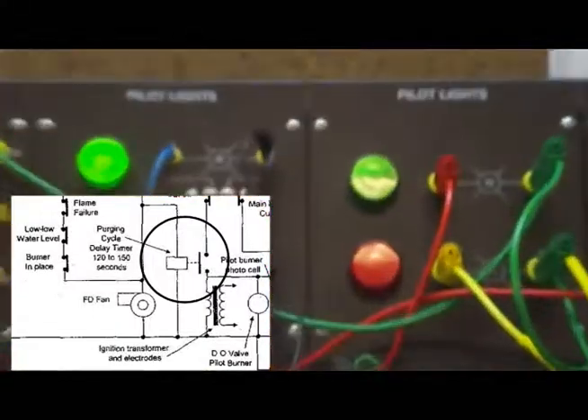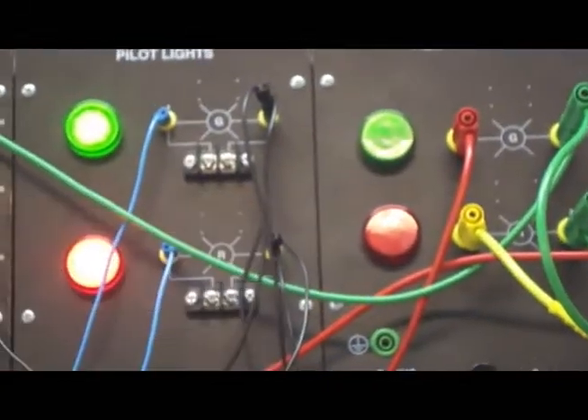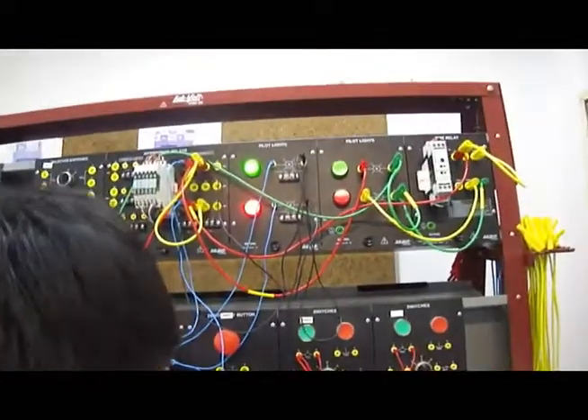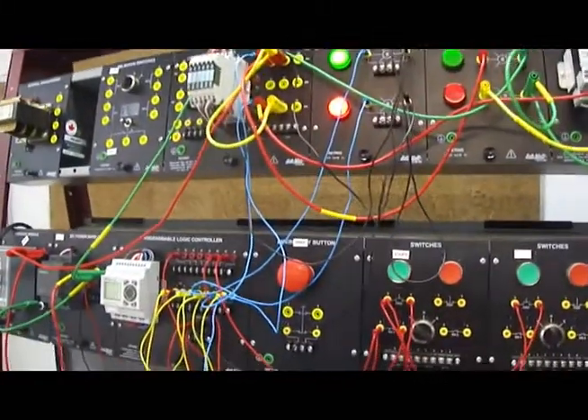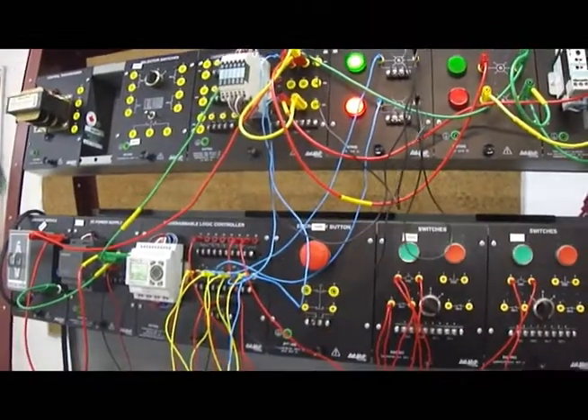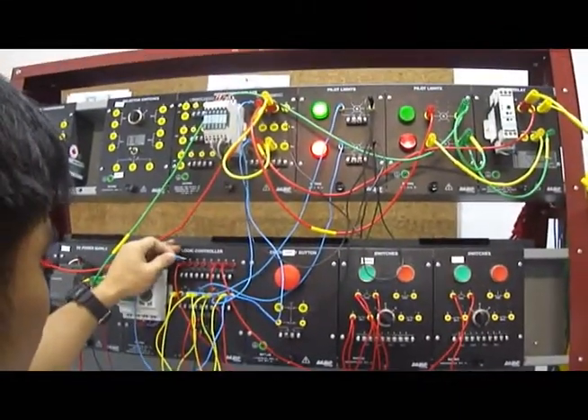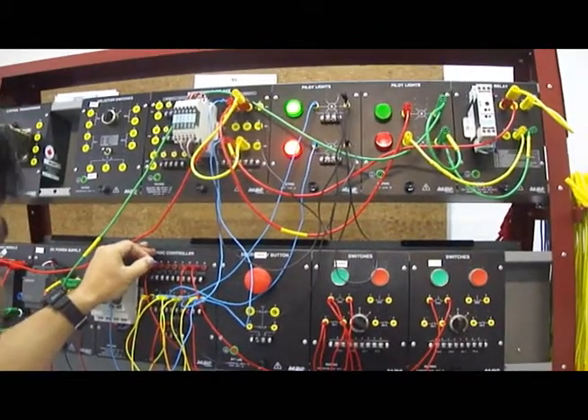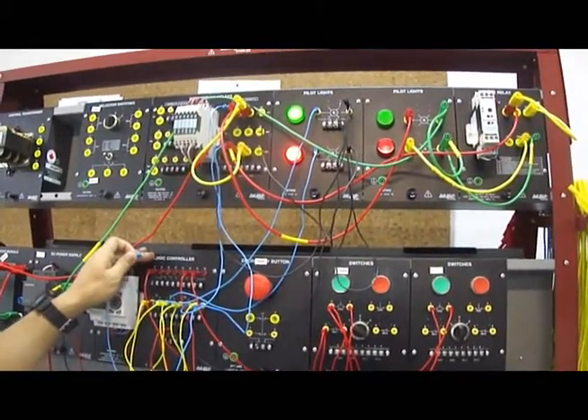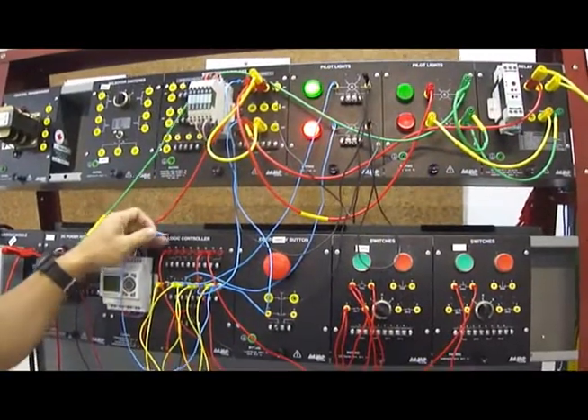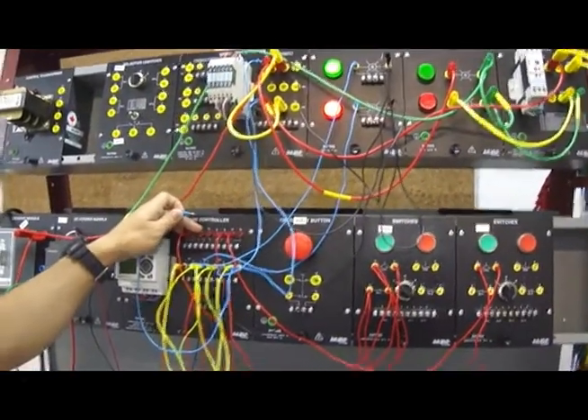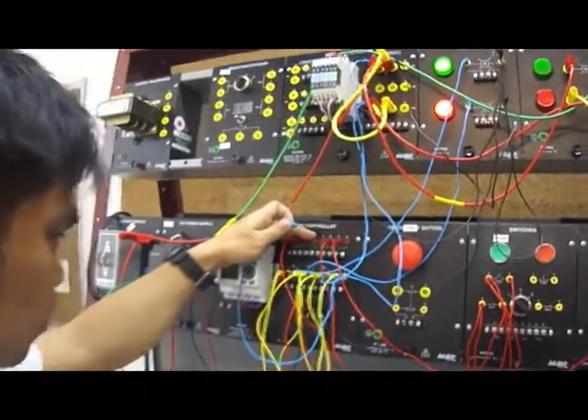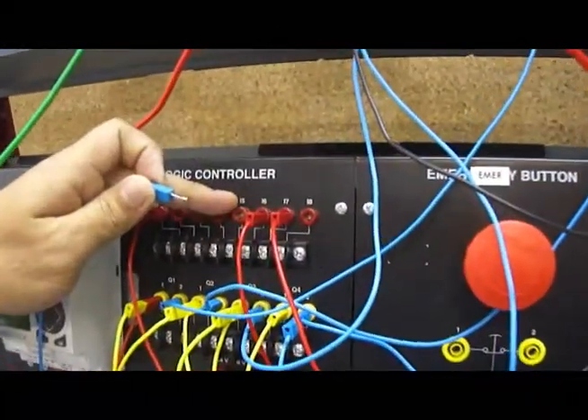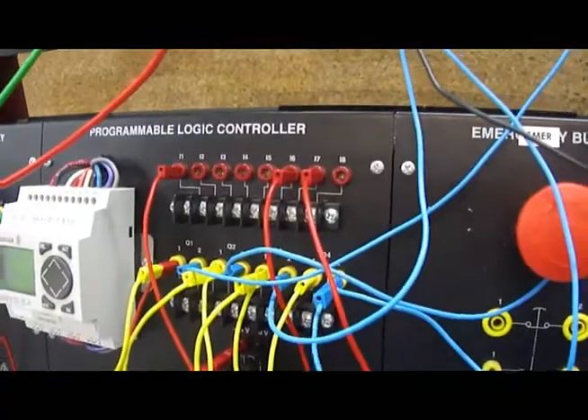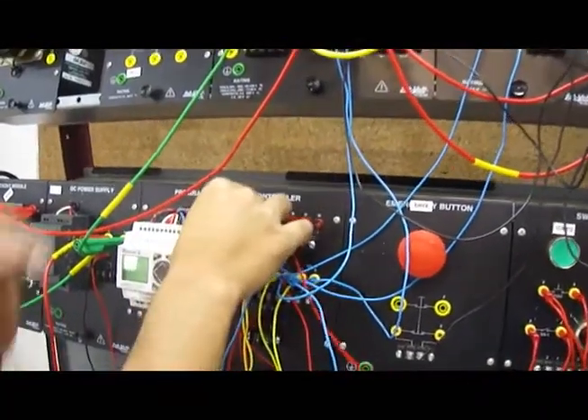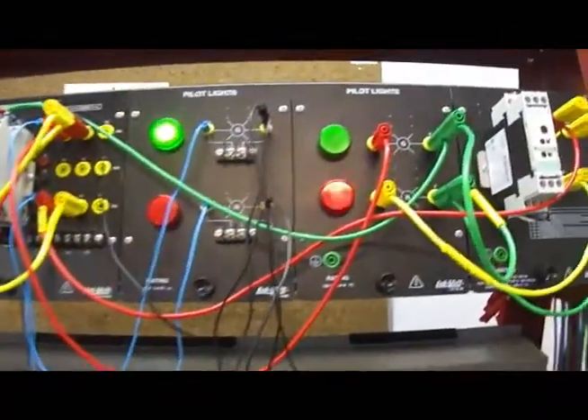The ignition is here, and we are giving all the simulations for the faults. If there are any faults, it will trigger and turn everything off. This is our fault for I2, the reset, I3 for the low oil pressure, I4 for the flame failure, and I5 for the low water level failure. If there's any fault, it will indicate that there's a fault in the system.